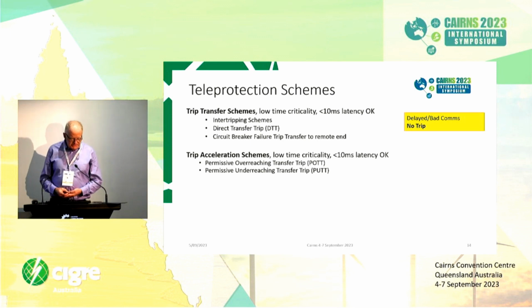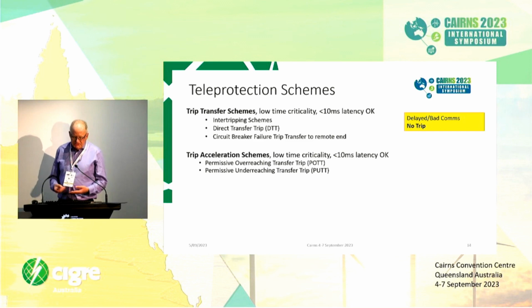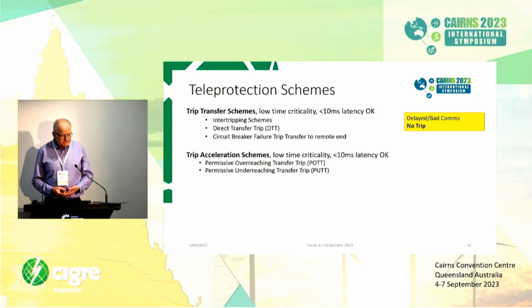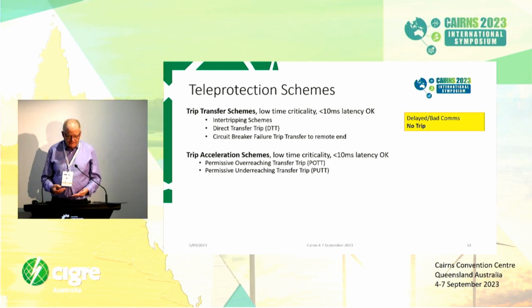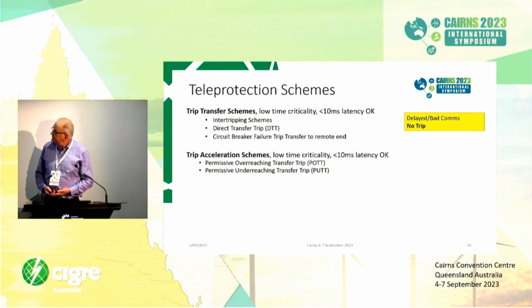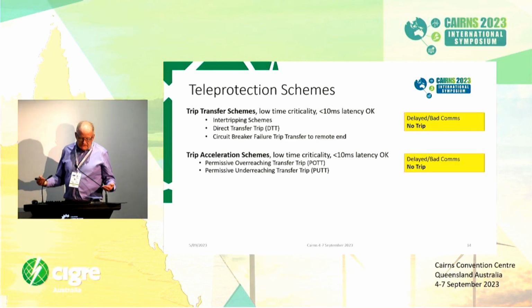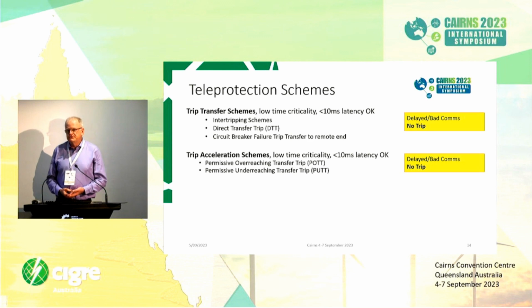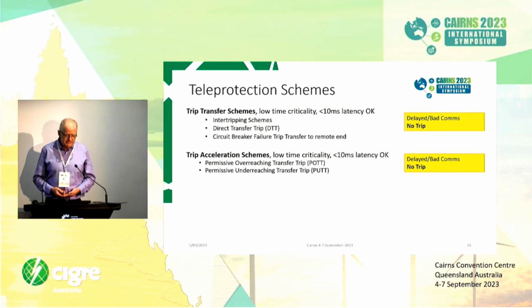Then we've got trip acceleration schemes. Once again, low time criticality, 10 milliseconds of latency still okay. Some examples are some of the permissive overreach trip transfer schemes like POTT schemes and then PUTT schemes. Once again, if that trip acceleration signal doesn't reach the remote end, all you're really going to do is delay the tripping of the line. So not great from a protection perspective, but at least you're not tripping off the transmission network again.